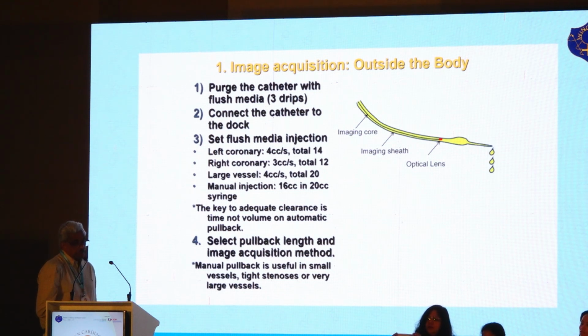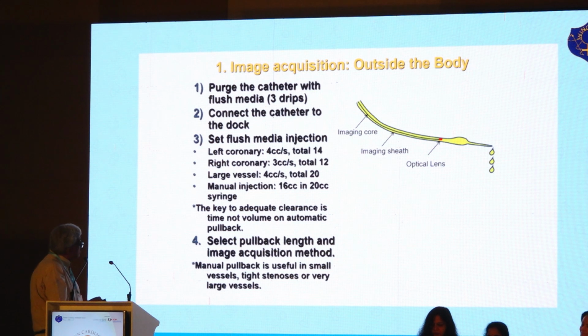The next thing, when I show you the picture next, is to select the pullback length and image acquisition mode. And this is very important before you start taking the picture. I like manual pullback in certain scenarios, when it's small vessels, very tight stenosis where sometimes the catheter won't move back on automatic pullback, or extremely large vessels, and sometimes in the ostium. So these are the areas where you should use a manual pullback. The catheter has an imaging core. Inside, there's a lens here, there's an imaging sheath, and there is a side port where the drip happens.